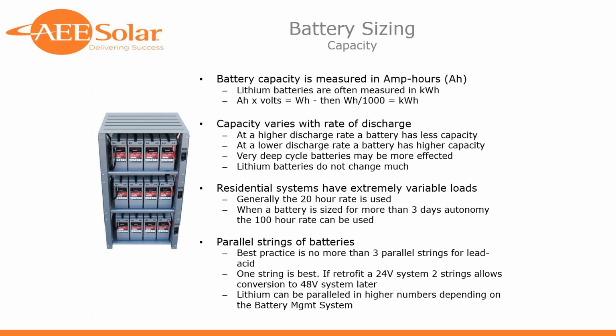Lithium batteries are different. Lithium batteries tend to come in blocks that are at the voltage that you're using, 48-volt block, and then you can parallel those. They have internal battery management systems that keep the balance between the cells, and you can go up to quite a number of parallel strings. I mean, some people are building megawatt-hour battery banks and containers, and with little teeny cells, and they're keeping them all balanced, and there's just thousands and thousands of them in parallel. So that works for those, just not for lead batteries.